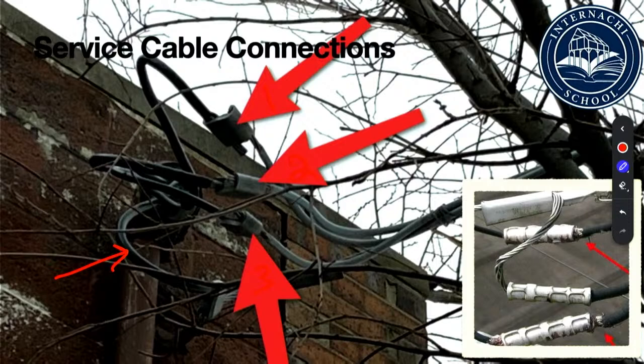If we look at the little box over here on the bottom right-hand corner of the screen, we only have 2 energized conductors. And then this one here is my messenger cable. That's my neutral. So I have a total of 3 wires. 2 of them are energized. One of them is the neutral. These are not 3-phase systems. They're single-phase systems. And that's where we get that 120/240 from.